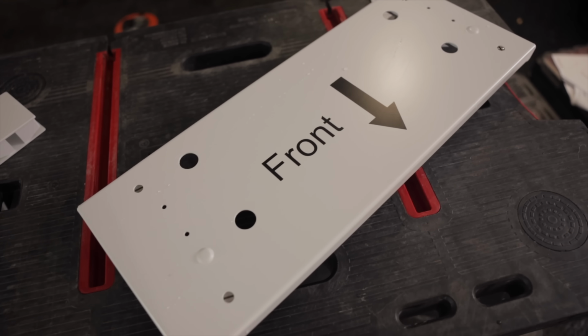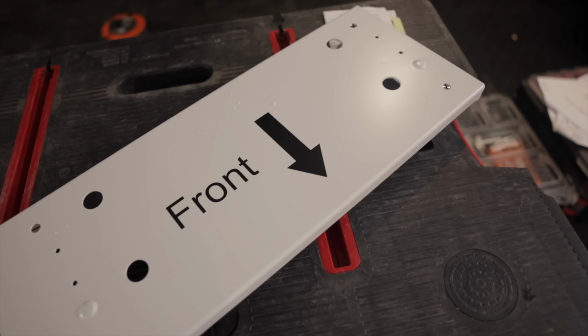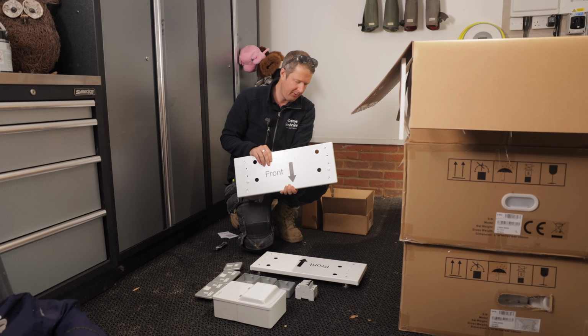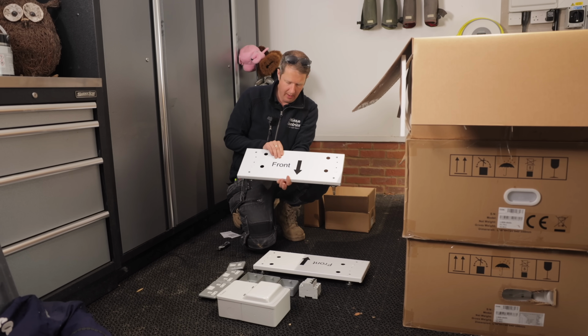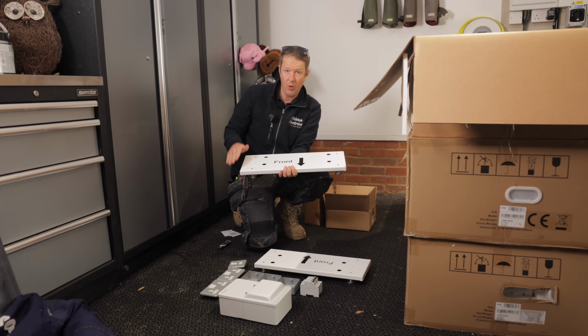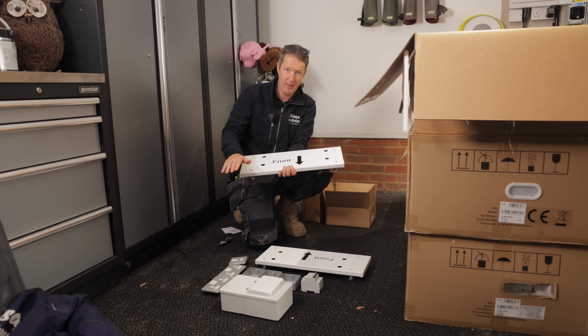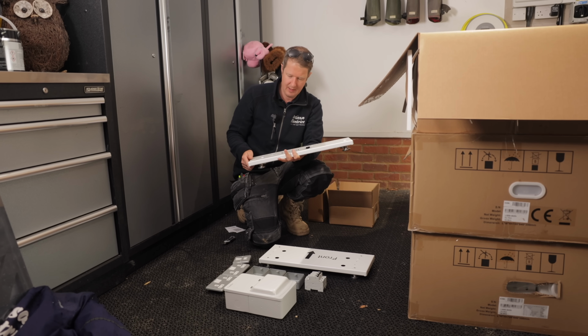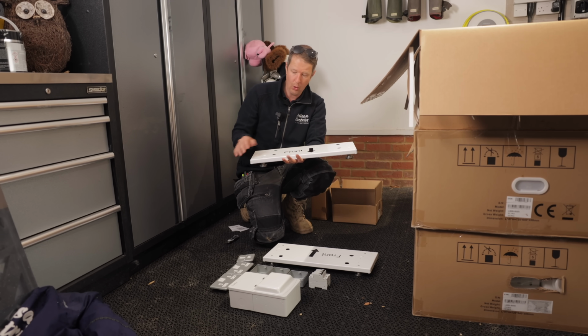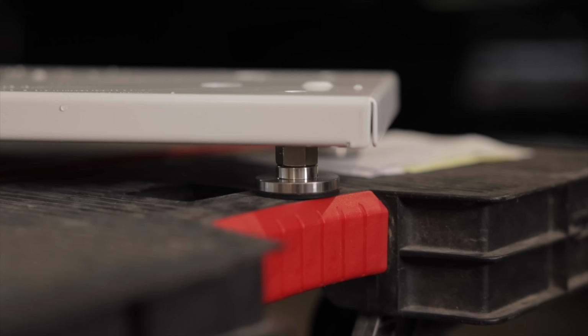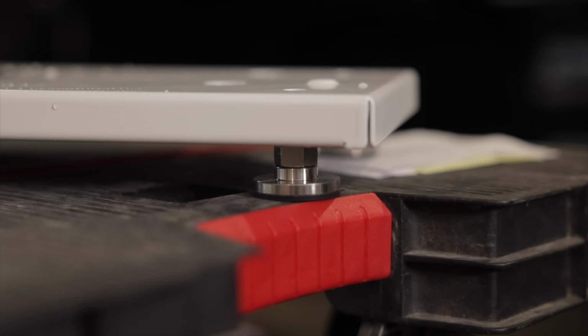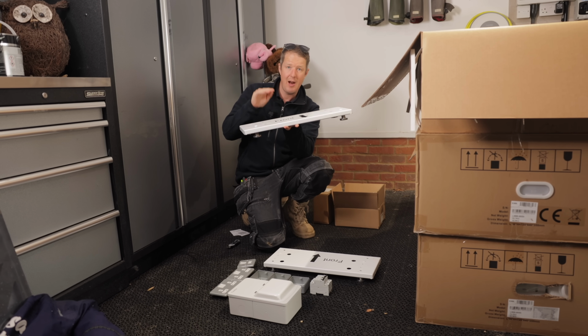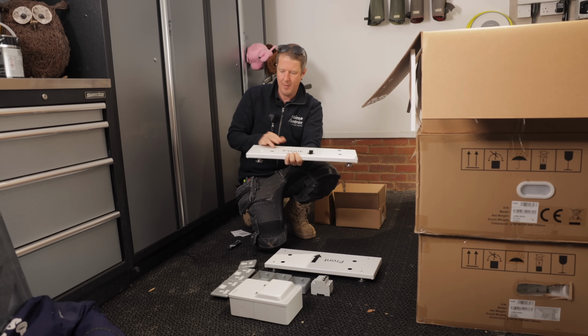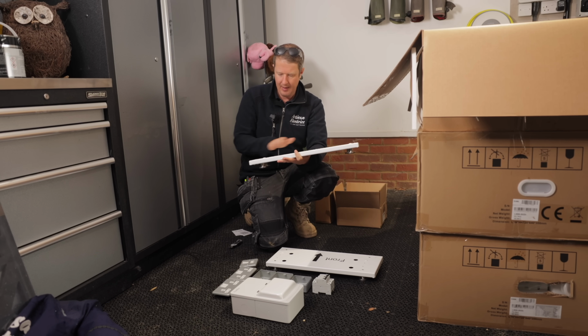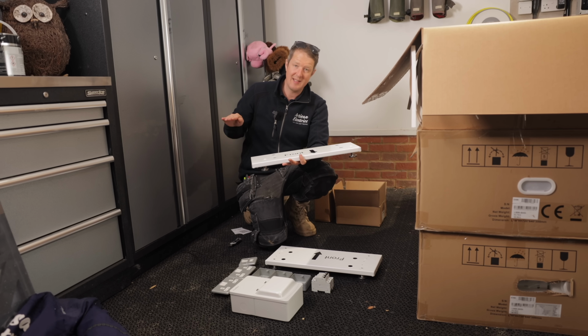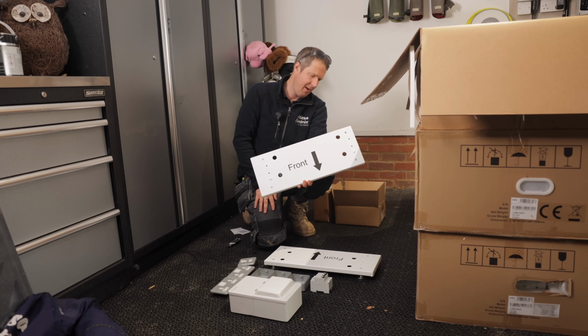So these are the floor stands. We're going to be fitting these as standard just to keep the batteries slightly raised up off the floor. They aren't absolutely essential, because if you've got a very nice flat, level floor, you can just mount the batteries directly on the floor. However, I like to install these for 2 reasons. One, if you've got an uneven floor, these little feet are adjustable, so it enables you to get the floor stand level and then stack everything up from there. It also means everything's slightly raised off the floor, which can be helpful - imagine if there's a bit of flooding or something like that. It just raises the batteries off the floor slightly, which I think makes everything a little bit safer.